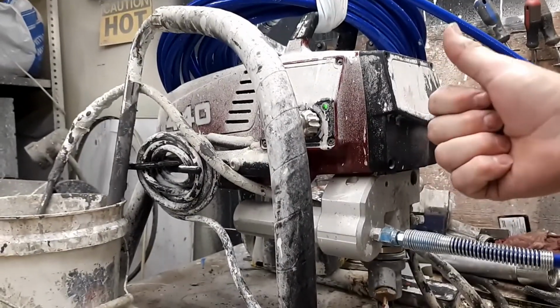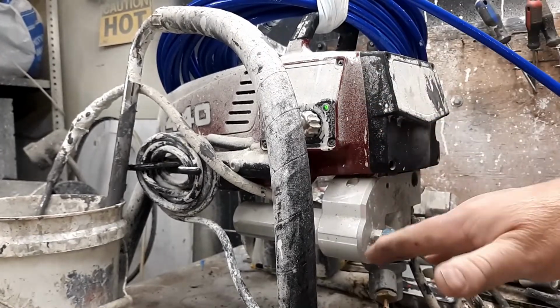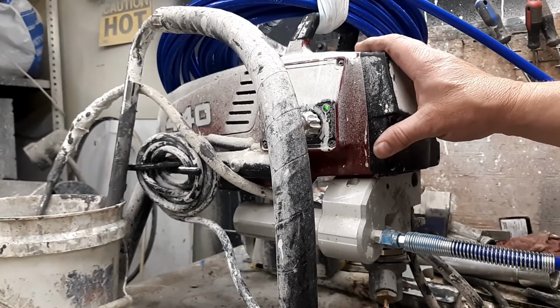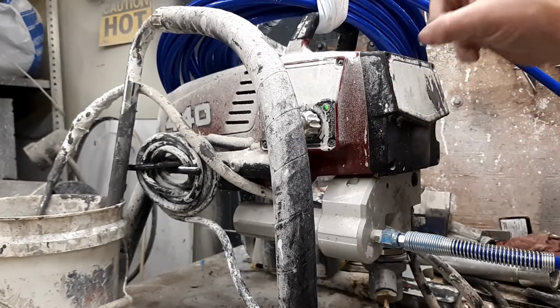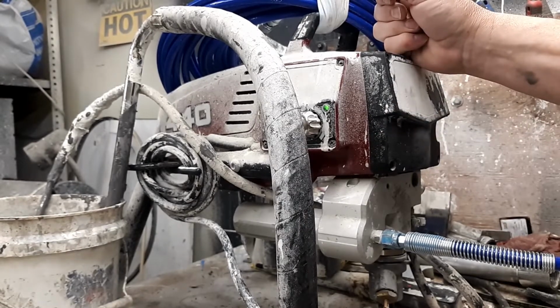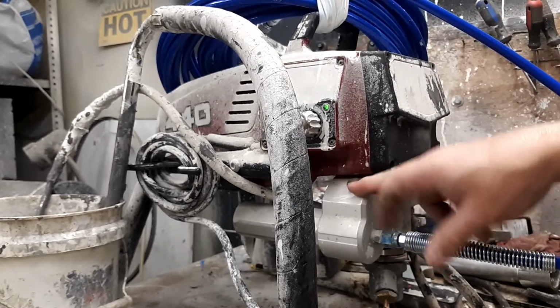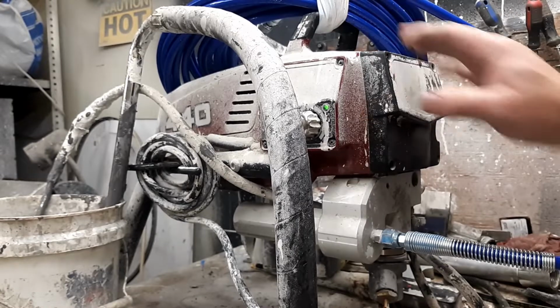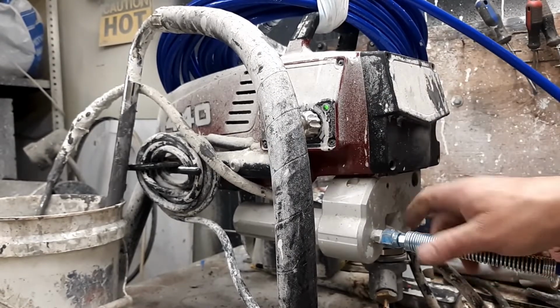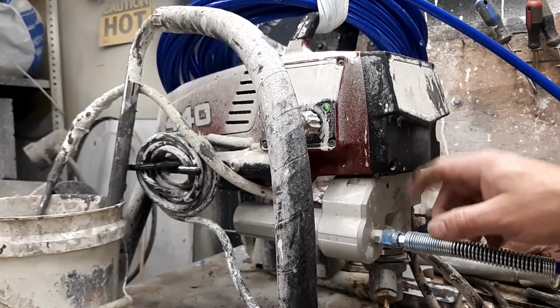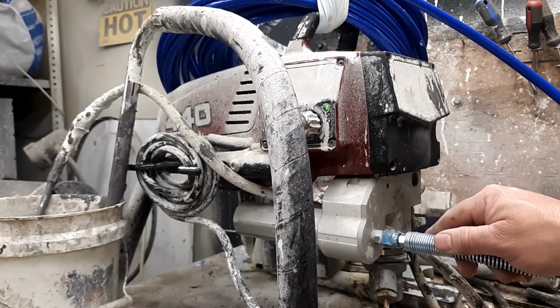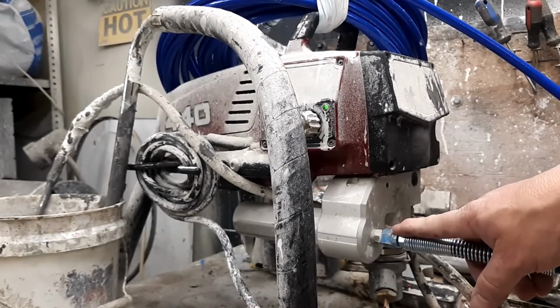When he's pulling the trigger, he's getting pressure, but it's fading down low because the machine is not turning on rapidly enough because you're getting a false reading on your transducer, which is in here. This is what measures the pressure. So I'm thinking this is where our problem is. So what I'm going to do is disconnect his hose, put my gun and hose on it, and we're going to get an actual pressure reading on it. And there's no need in you watching me take this off and put my hose on.